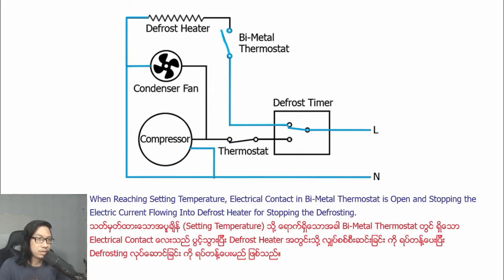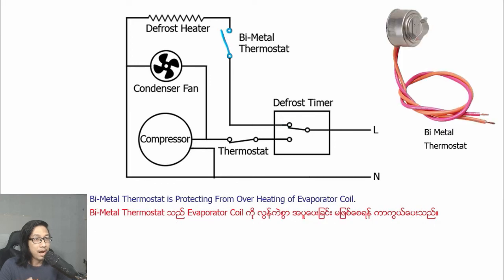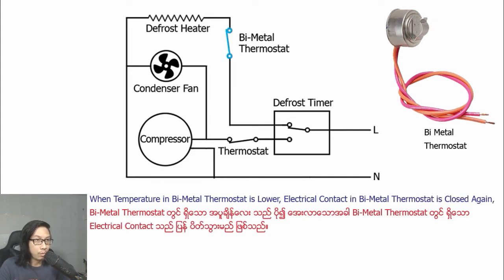When the set temperature is reached, the electrical contact in the bimetal thermostat opens, stopping the electric current flowing into the defrost heater and stopping the defrosting. The electrical contact for defrosting remains closed until the set time interval for defrosting is finished. When the temperature in the bimetal thermostat drops lower, the electrical contact in the bimetal thermostat closes again.